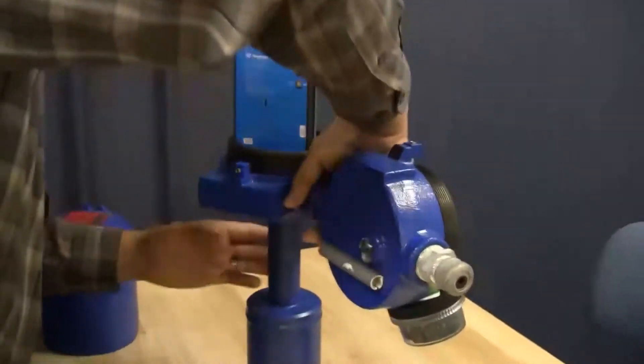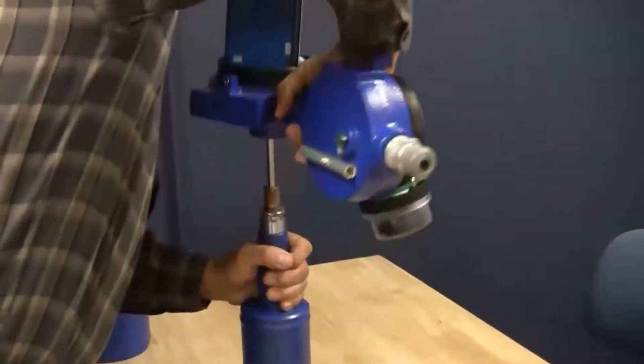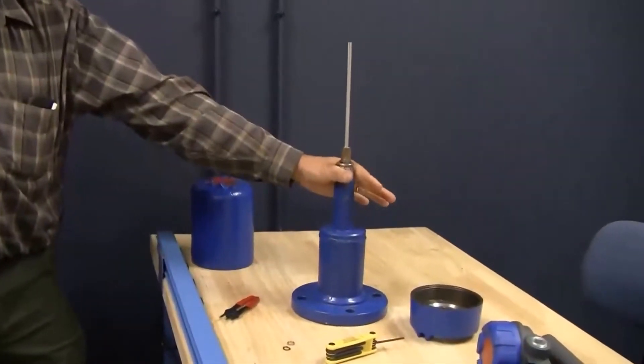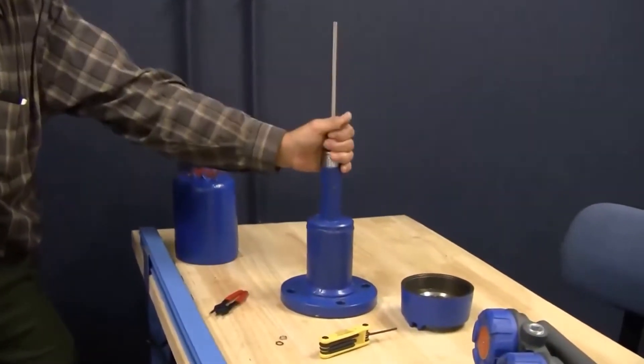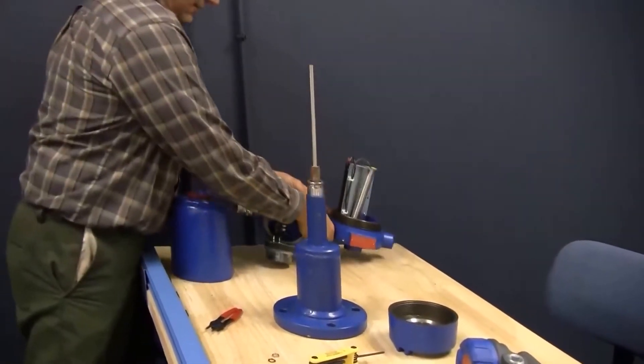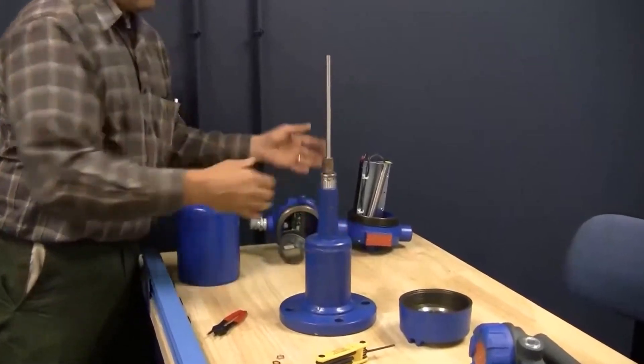Mine's a little tight here, so I'll try to hold this. There we go. And that lifts the entire assembly off. Now notice, you still have your enclosing tube. You have not broken into the process. This entire procedure did not break into the process. We did not open up the pressure boundary to do this.